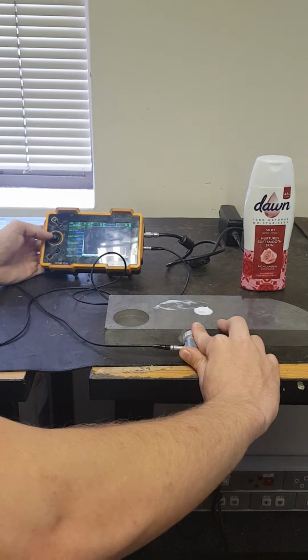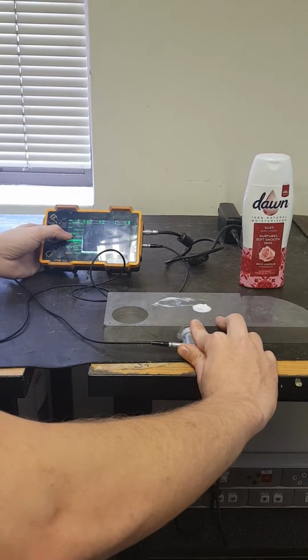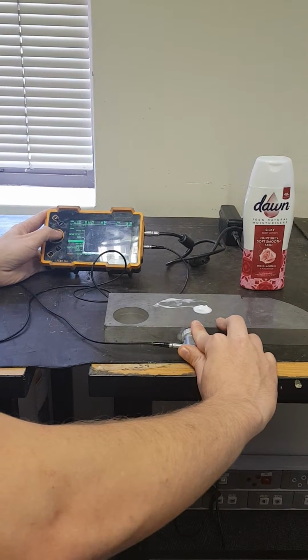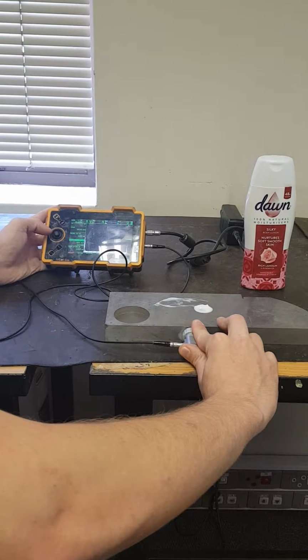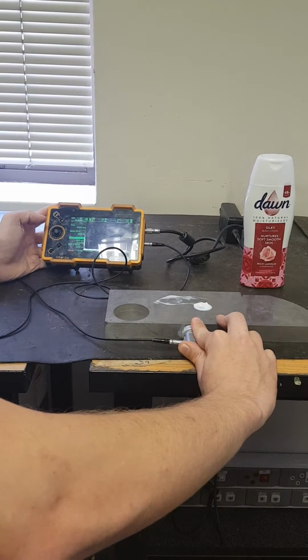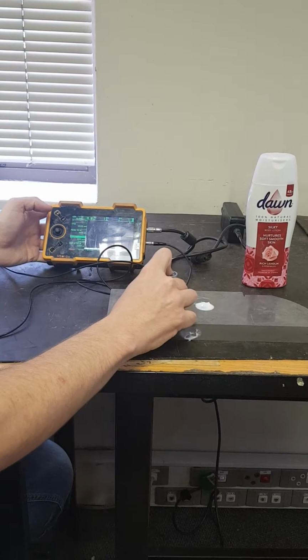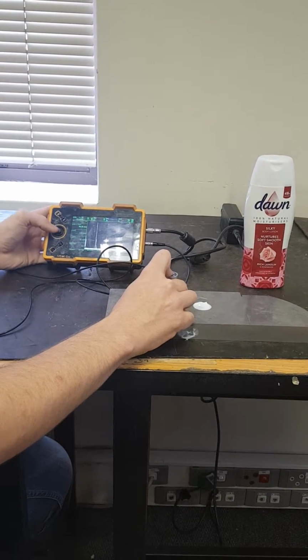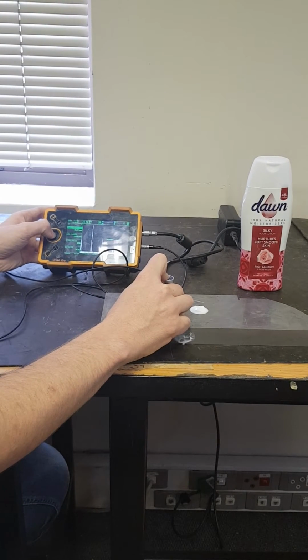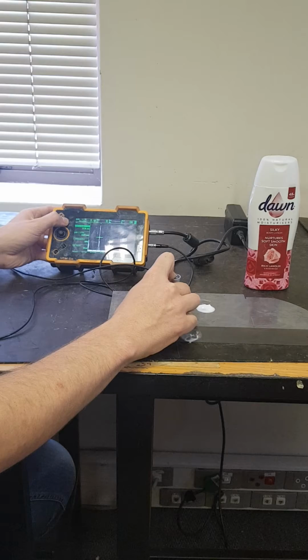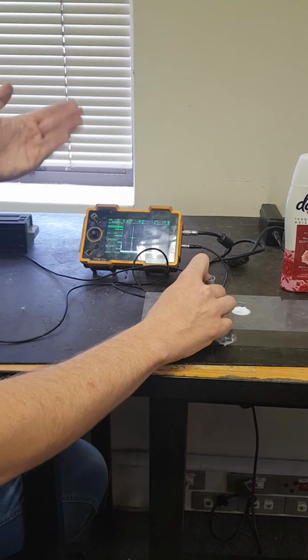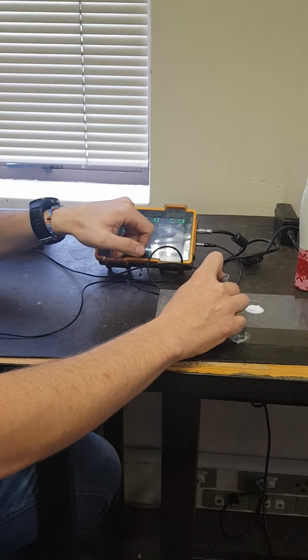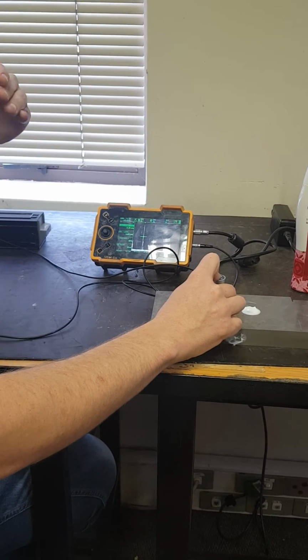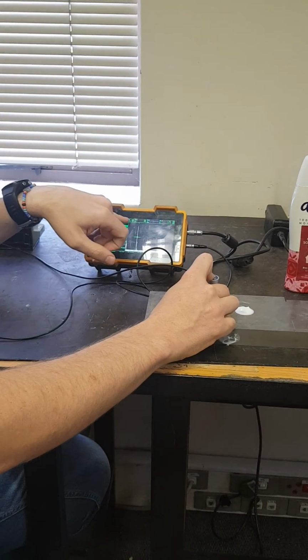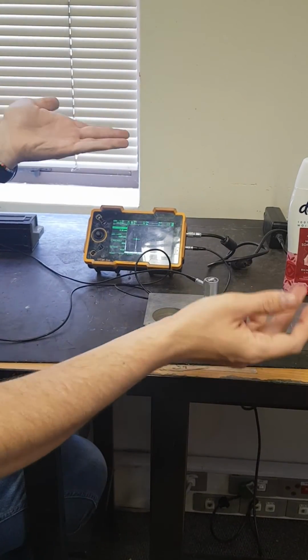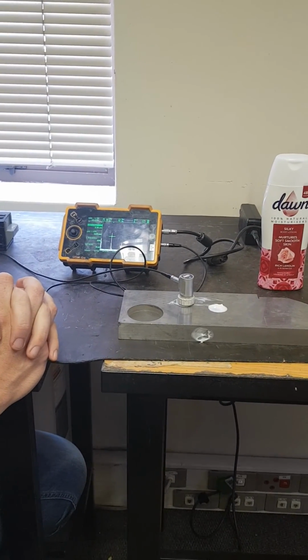So for the second echo, we don't adjust the probe delay, we adjust the velocity just a little bit, so this gives us 100. All right, now we go back to the 25. We move our gate over this as well. It's very important that your gate is moved over the echo you want to measure, otherwise you will not get a measurement. It's also very important that you can see the peak, otherwise the measurement won't be accurate. And now we see it's 25 there, which means this set is now essentially calibrated. Good stuff.